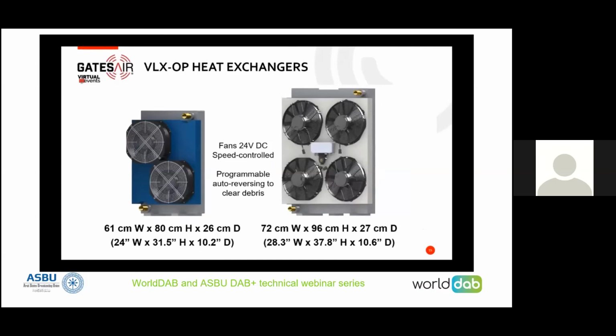Now heat exchangers, for some products, can be very large, but as I mentioned, space is at a premium in a transmitter site, so reducing the footprint's a good way to save on your operational costs. Now, in this case, we see a couple different versions dependent upon how much power you're running, both with redundant fans. So the smaller one's about 60 by 80 centimeters, the larger one's about 70 by 96. So as you can see, very, very compact. They can be mounted vertically or horizontally.